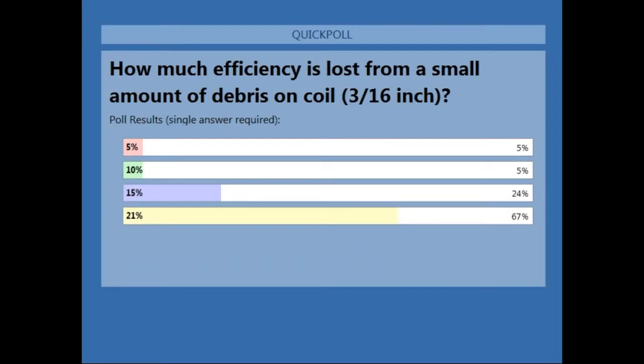It looks like the majority of you did get it right. About 1/5 of the efficiency of the air handler unit is lost if the coil is fouled just 3/16 of an inch with dust or debris. Think about how small 3/16 of an inch is on the coil — that's like the width of a business card. If you had that kind of fouling across the coil, you're losing 20-21% of your energy efficiency right there.